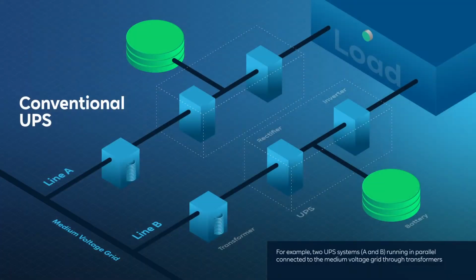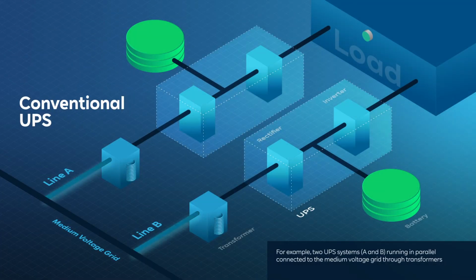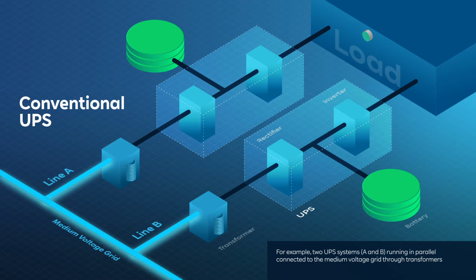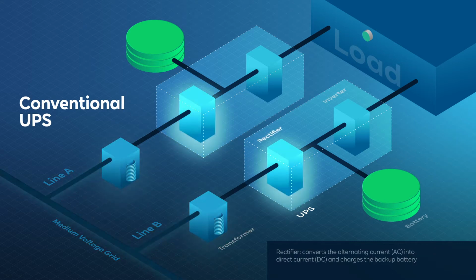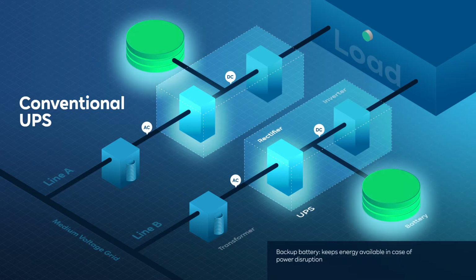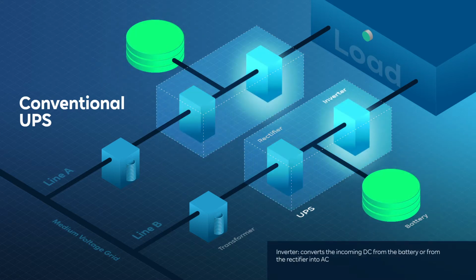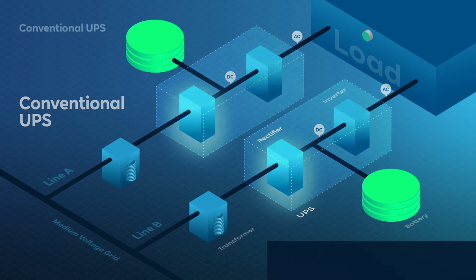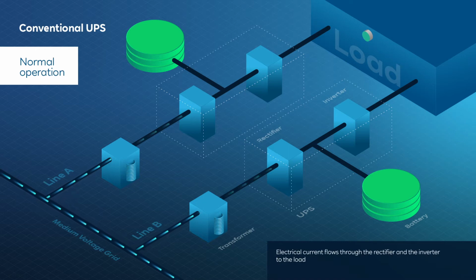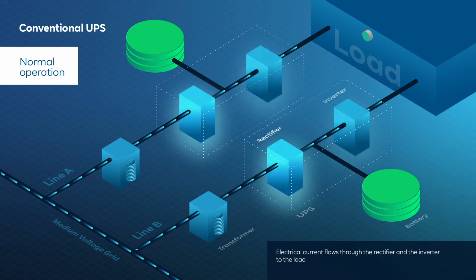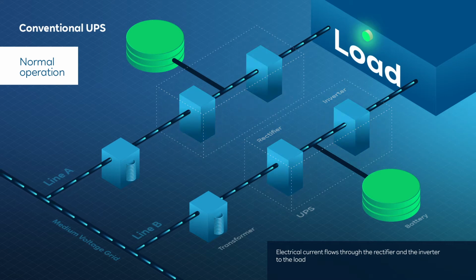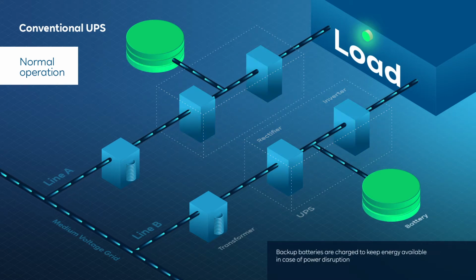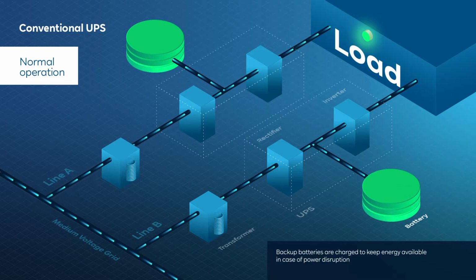For example, two UPS systems, A and B, running in parallel are connected to the medium voltage grid through a transformer. The UPS contains a rectifier that converts the incoming alternating current, AC, to direct current, DC, and also charges the backup battery. The inverter converts the incoming DC from the battery or from the rectifier to alternating current. When the UPS is in normal operation, the electrical current flows through the rectifier and the inverter to the load.